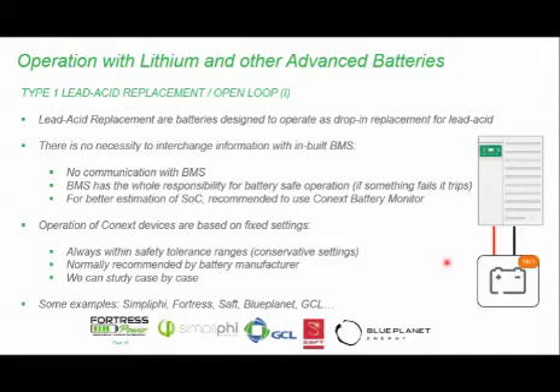Open loop is typically when you connect your batteries to your inverter and match the specs of the battery to the inverter, going into the inverter to set your bulk, absorption, float voltages, charging current, discharge current, and all those individual settings. Those are typically referred to as open loop settings. This is typically what you do for lead acid batteries, like flooded, gel, AGM, or even lithium-ion batteries that don't have a BMS connected to them.